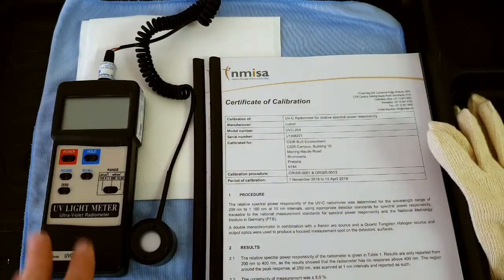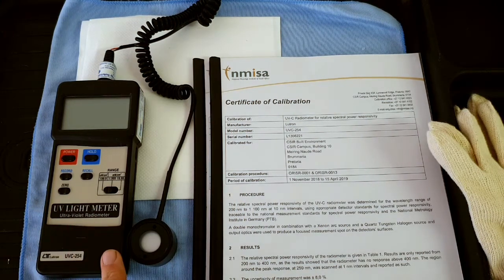So while I've got you here, I just want to quickly discuss with you some concerns, considerations and aspects when using and selecting UVC radiometers. I've said this one is probably not the best you could buy on the market. It is good value for money though, as long as you know what you're working with. It claims to be a UVC radiometer. You can see right here it says UVC 254 nanometers. A little bit suspicious. 254 nanometers is exactly the peak output of low pressure mercury vapor lamps. So what it's claiming is that the filter in the sensor filters out all UV except for 254 nanometers.